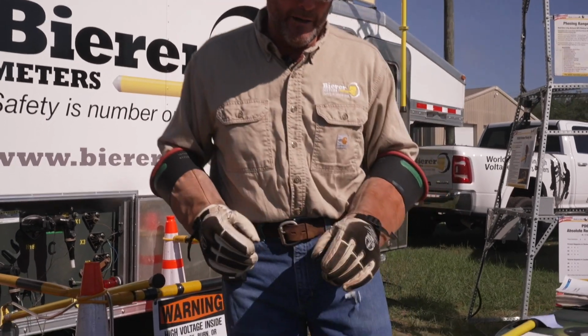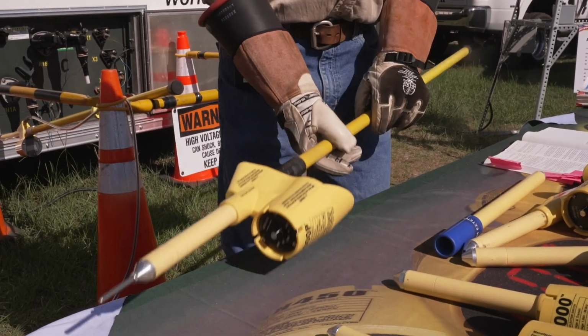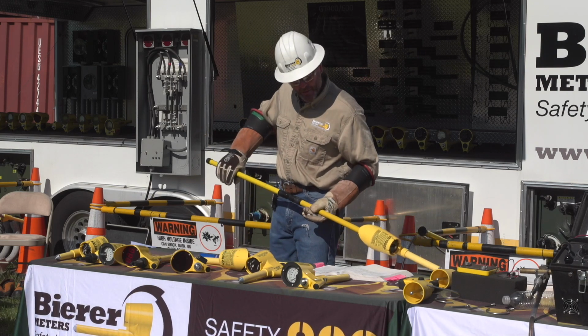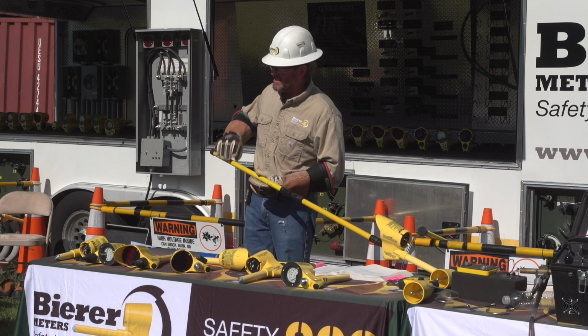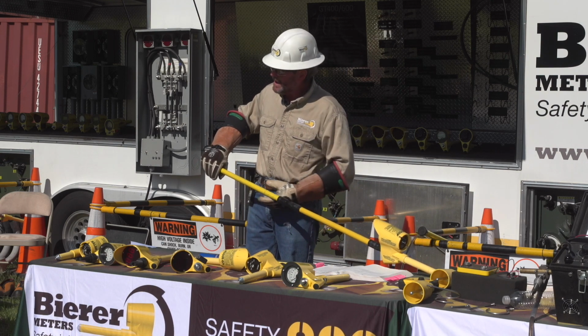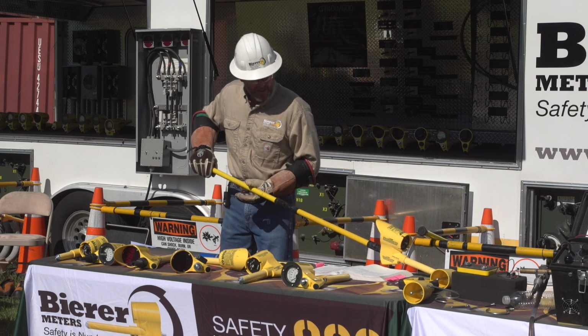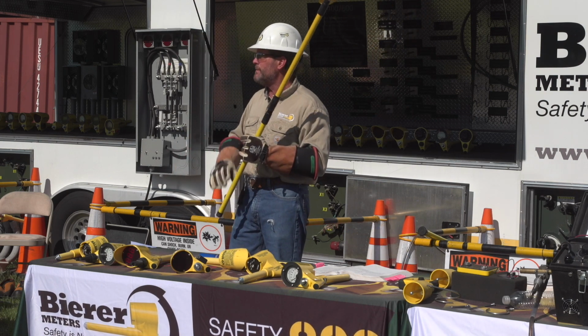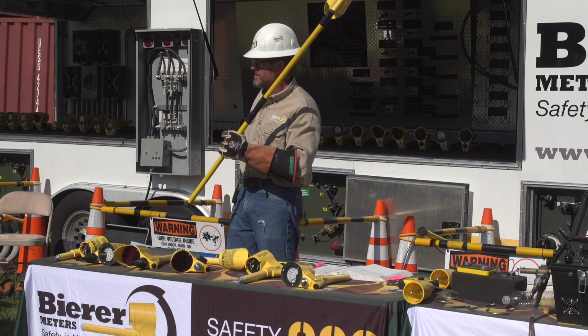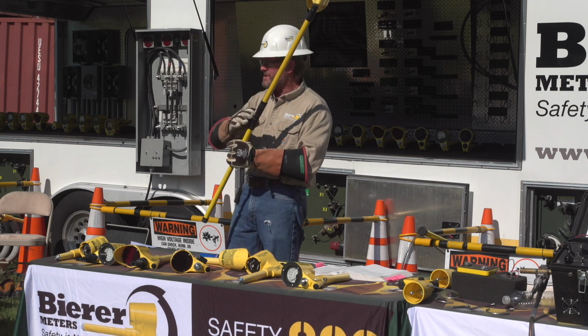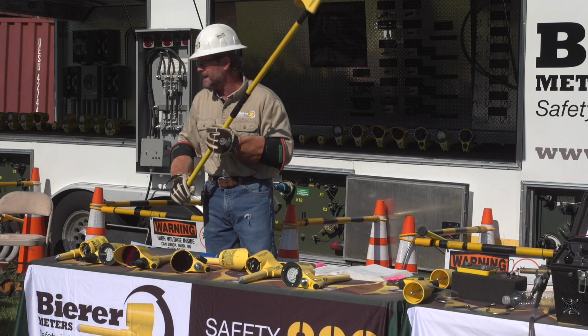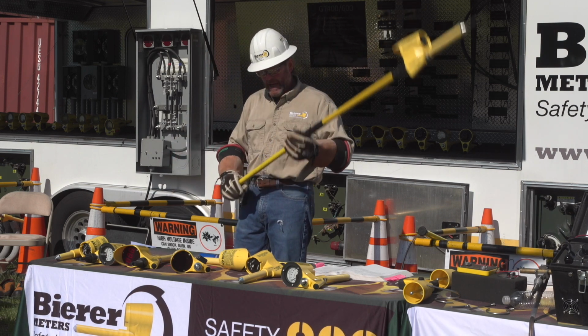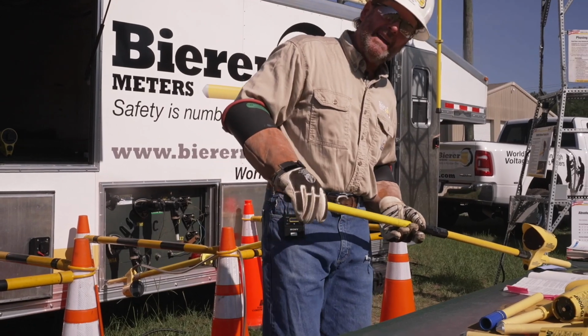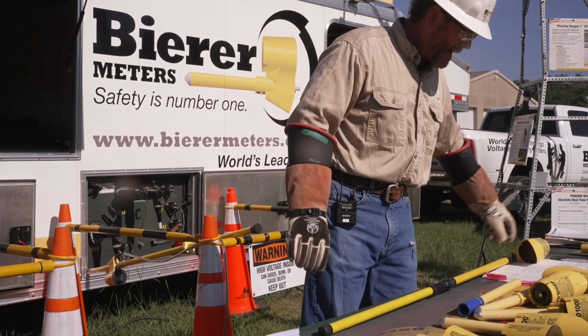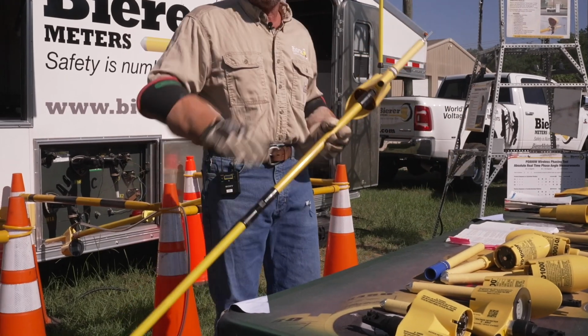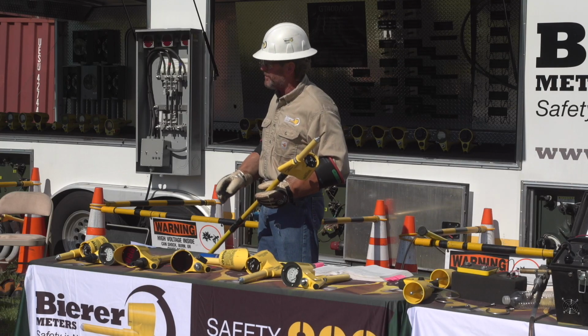So you got your PPE on, and typically a lineman, when out in the field, is going to use these tools, and you always got to remember that tool equation functionality: X plus Y equals safety and accurate information gathering. So the lineman's going to be back on his hot stick minimum 31 inches because of arc flash measurements. You're going to be minimum 31 inches back, and we recommend 36. I like 36 better, because the X, the conductor, plus Y, tool functionality, needs to stay that way, and that always equals safety and proper information gathering.